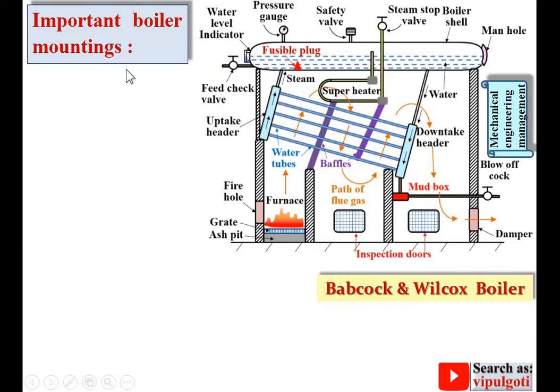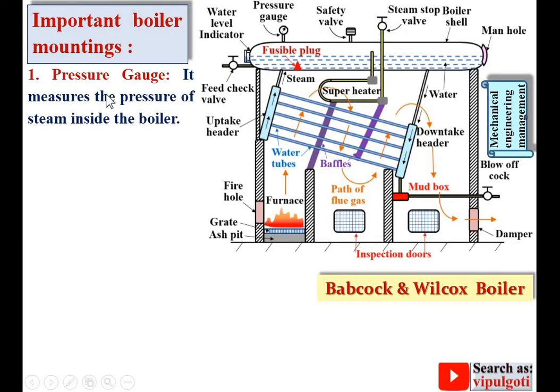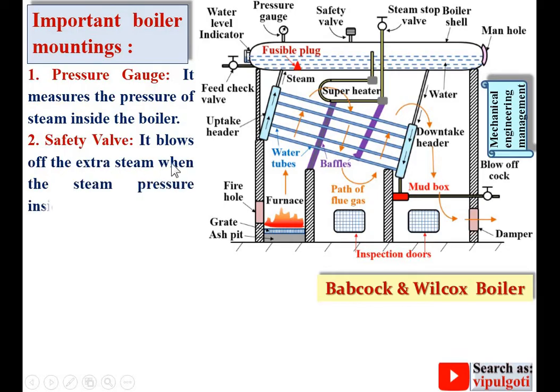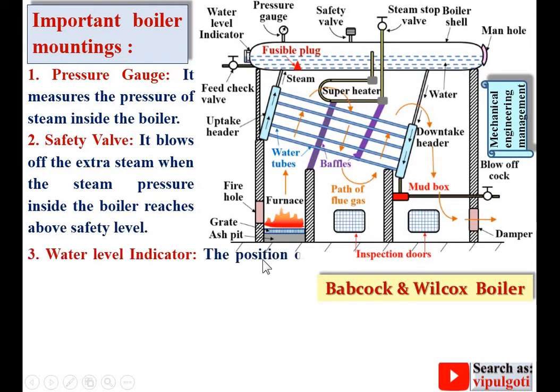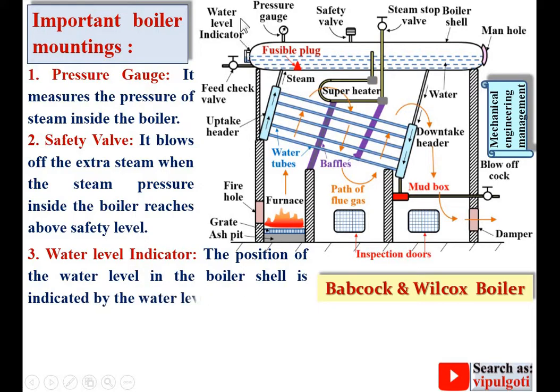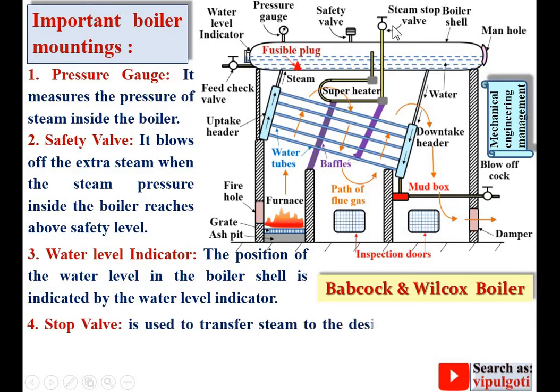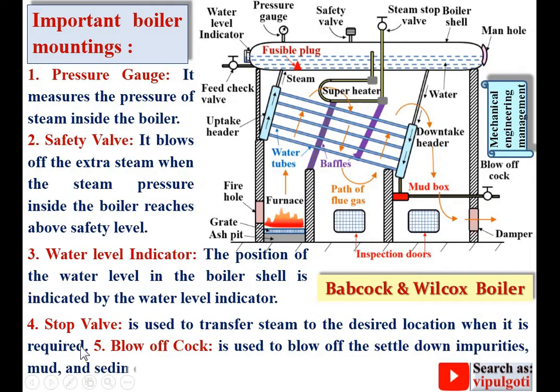Now the important boiler mountings. First, the pressure gauge — it measures the pressure of the steam inside the boiler. Second, the safety valve — it blows off the extra steam when the steam pressure inside the boiler rises above the safety level. Third, the water level indicator — it indicates the position of the water level in the boiler shell, so you can see the water level inside. Fourth, the stop valve, sometimes called the steam stop valve — it is used to transfer steam to the desired location when required. Fifth, the blow-off cock — it is used to blow off settled impurities, mud, and sediments present in the boiler water with the help of the mud box.